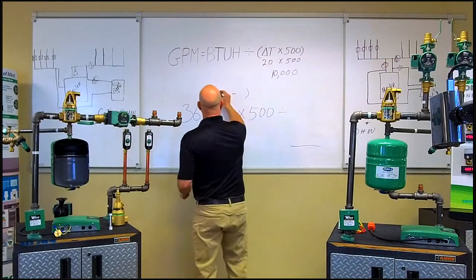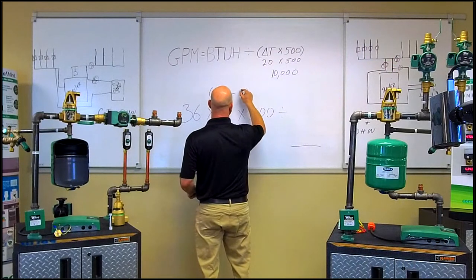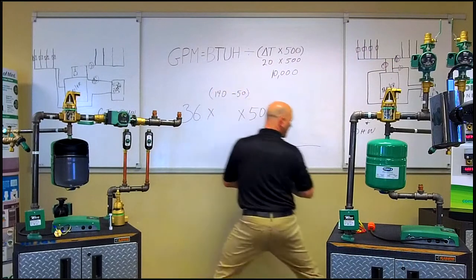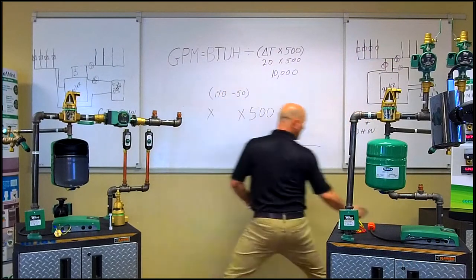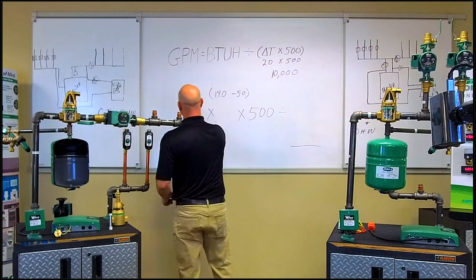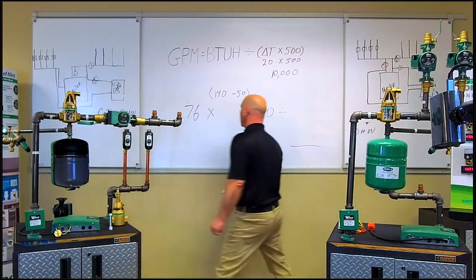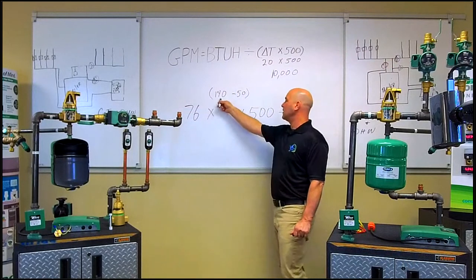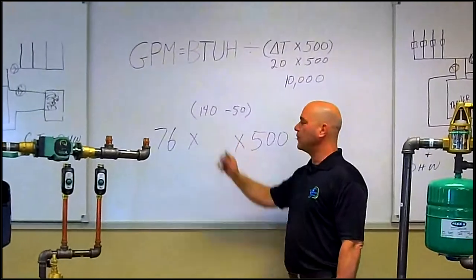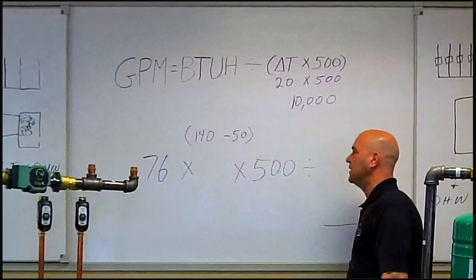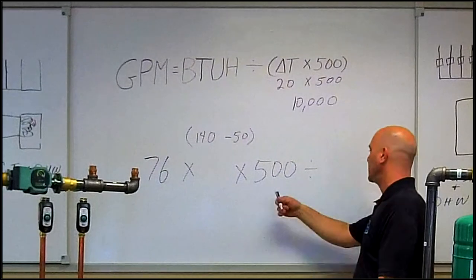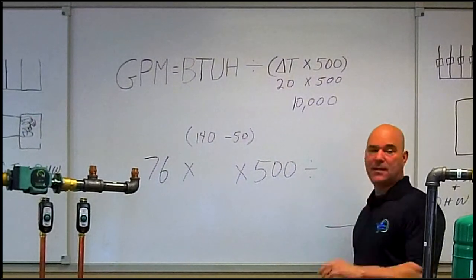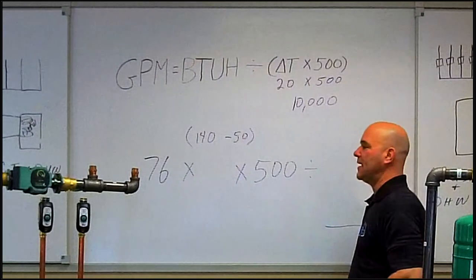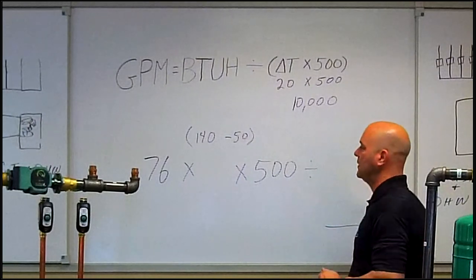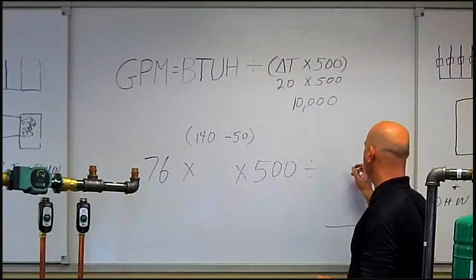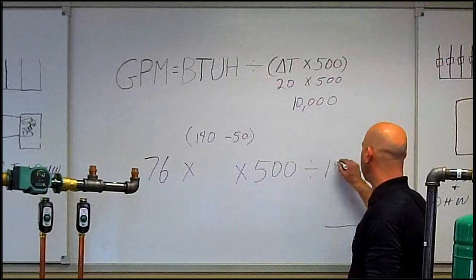Okay, so a little bit more of a commercial type application, okay? Because it's a commercial type application, we have an 80 gallon tank in there with 76 gallons of storage, 50 degree incoming water, 140 degree going out to the dishwasher, and then there's a preheater on the dishwasher. Okay? This time we have a circulator on there. We have a 0010, which is pretty common on indirects. So that 0010 is moving, we're going to call it 15 gallons per minute.